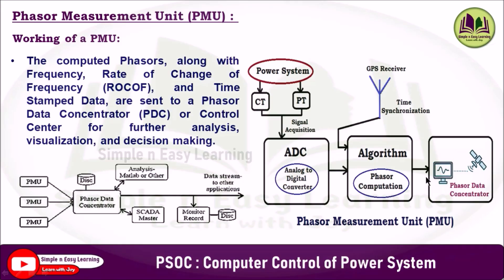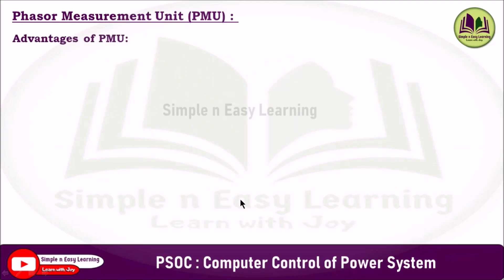The computed phasors, along with frequency, rate of change of frequency, and time-stamped data, are sent to the phasor data concentrator or the energy control center for further analysis, visualization, and decision making. In the phasor data concentrator, all outputs of the PMUs are connected, and the data is analyzed using MATLAB and other simulation software used in power systems. This is connected to the SCADA system to monitor and control, and the results are recorded in the master computer unit, with data streamed to other applications.